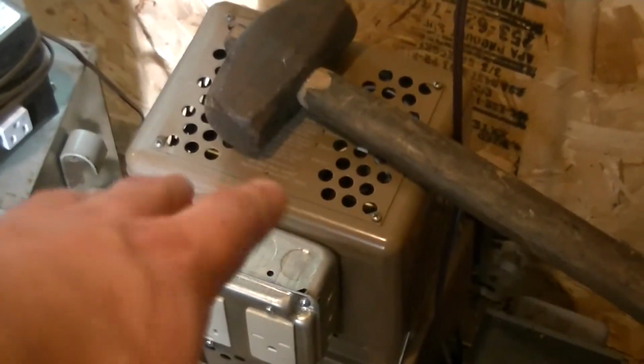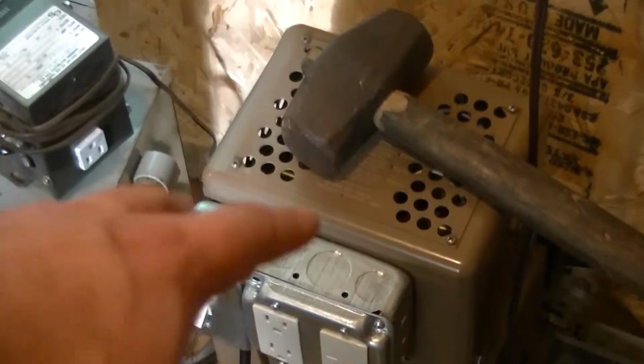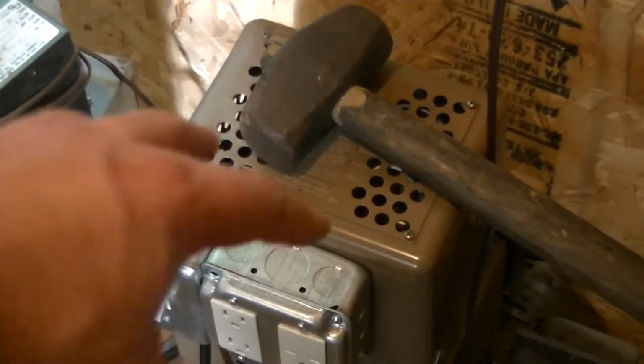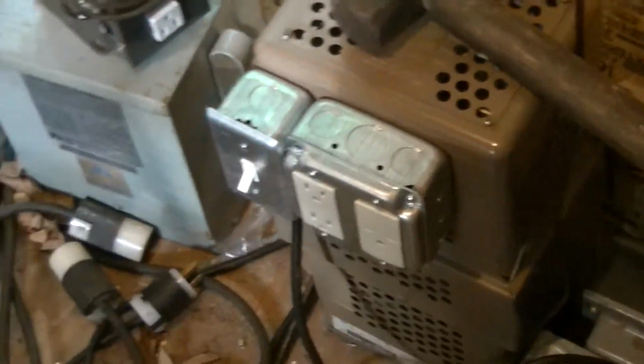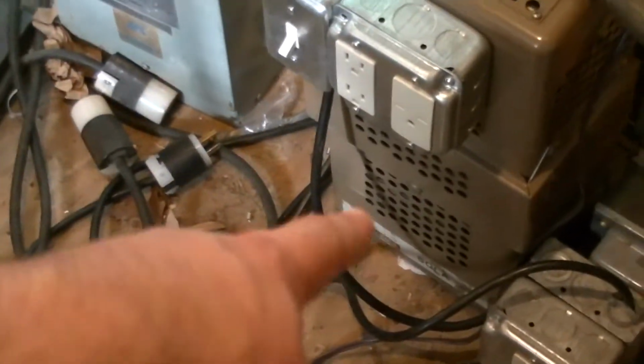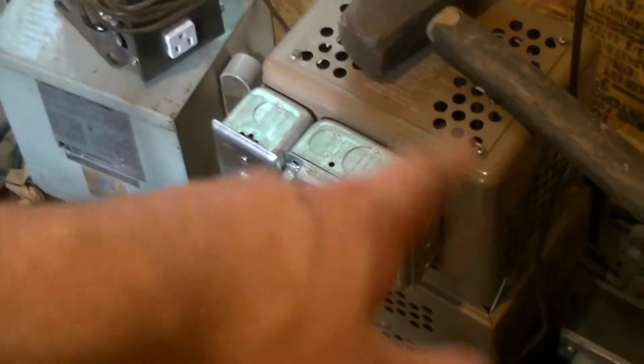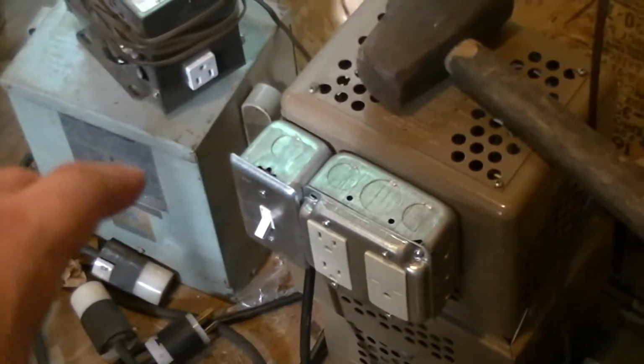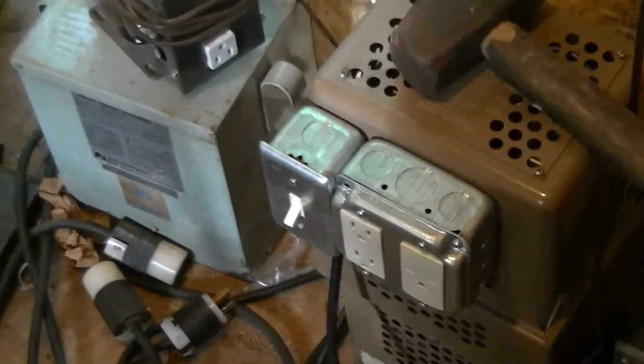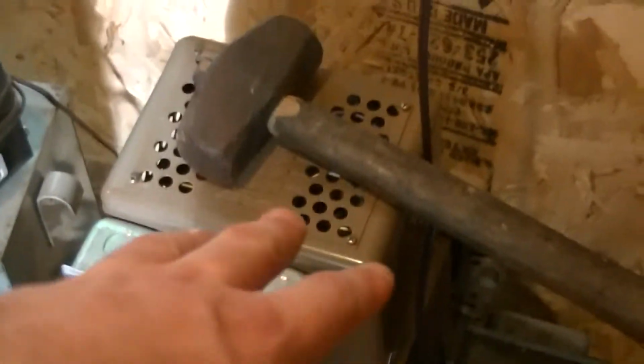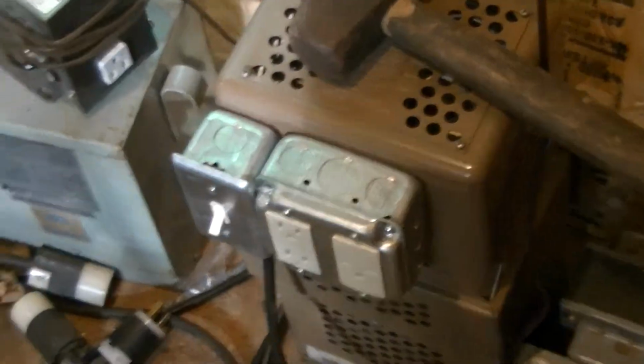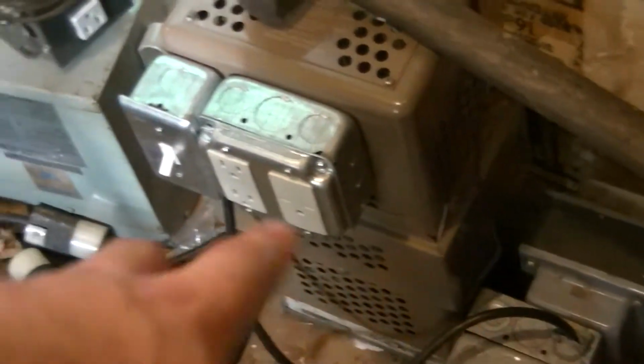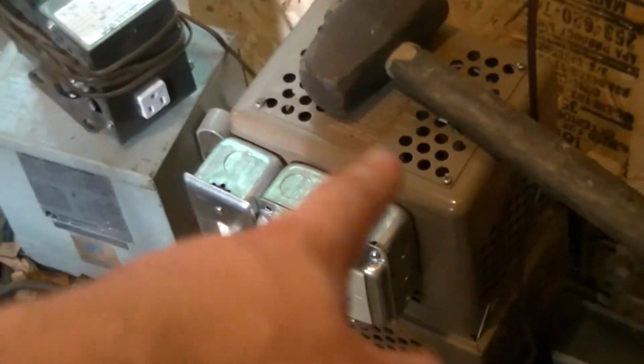That's just due to the core regulation mechanism of these, meaning that the core operates in saturation, because that's in conjunction with the LC tank circuit formed by the capacitors that are in the bottom of the transformer, and an auxiliary winding that the secondary winding of the transformer is tapped off. So in the case of a ferro-resonant, the input and output really aren't interchangeable, unlike with a conventional isolating transformer. Also, these guys are stupid expensive.